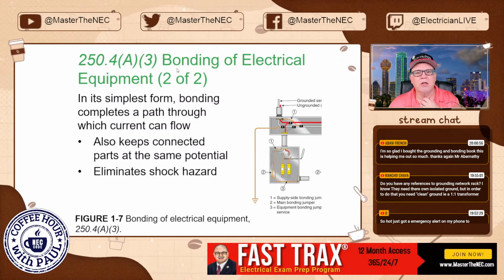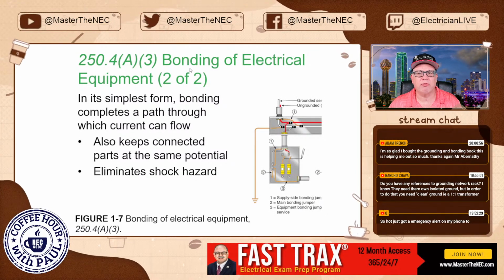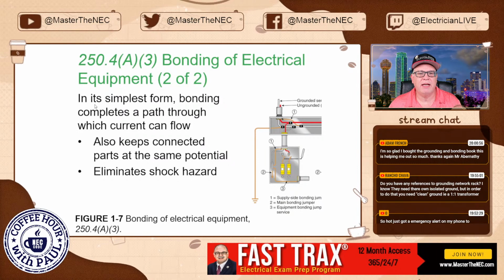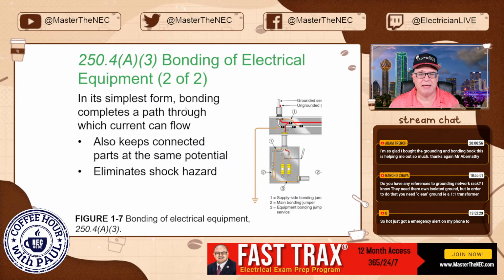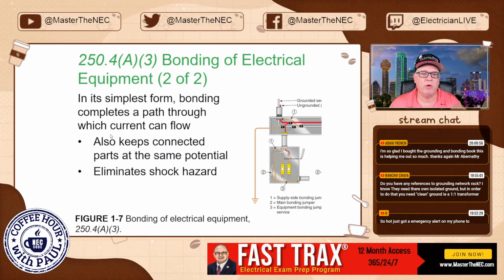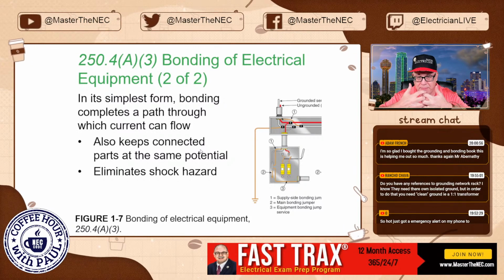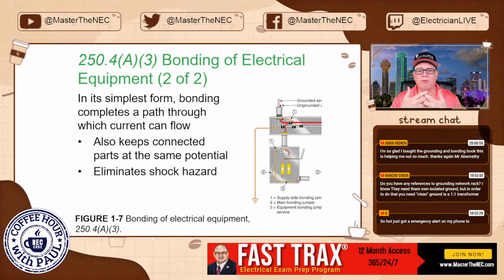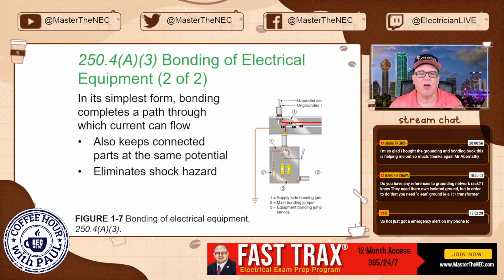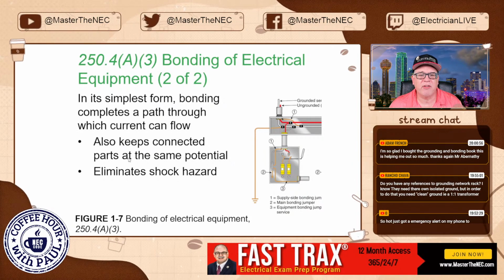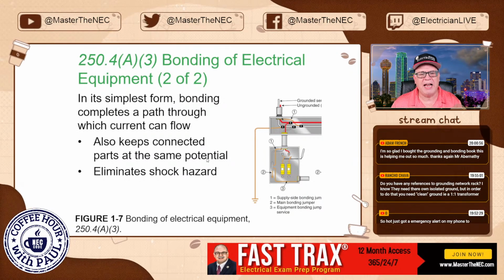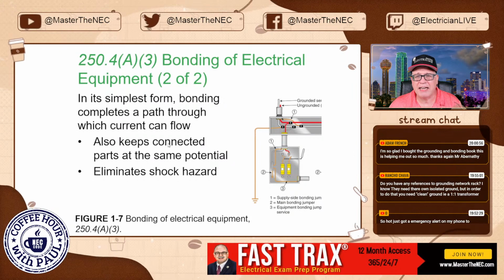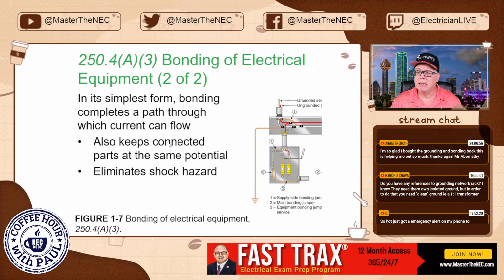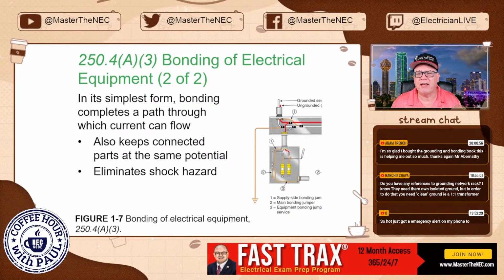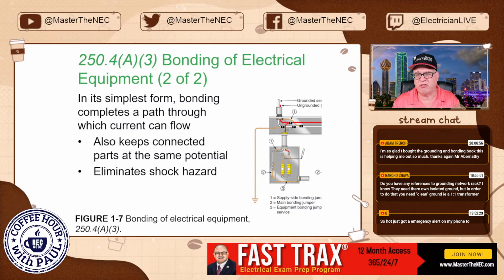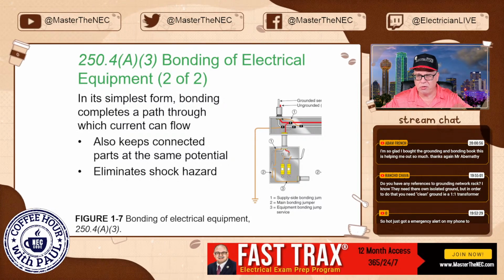All right, 250.4(A)(3), bonding of electrical equipment. In its simplest form, what does bonding mean? Bonding completes a path through which current can flow, tying metal parts together so current can flow freely. It also helps connect parts at the same potential, and it eliminates the shock hazard. I will venture to say that it's only as good as those connections. So it's going to eliminate it.